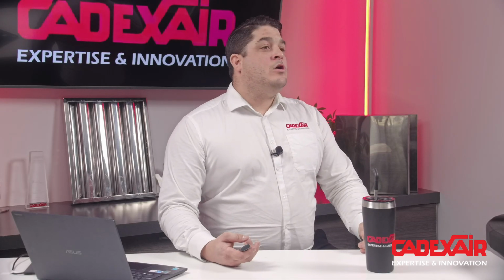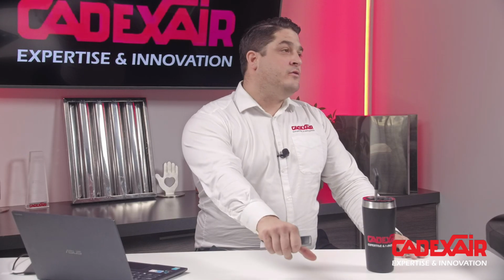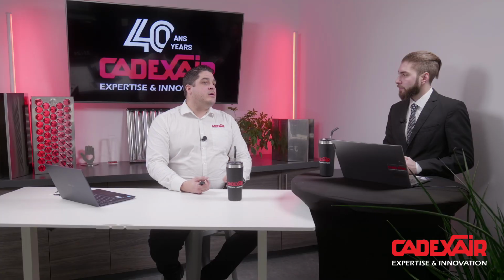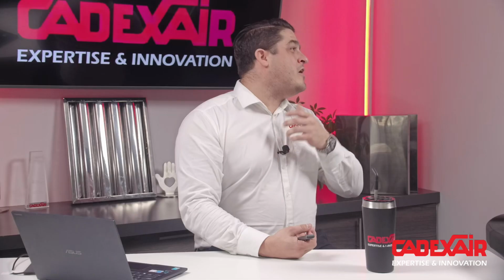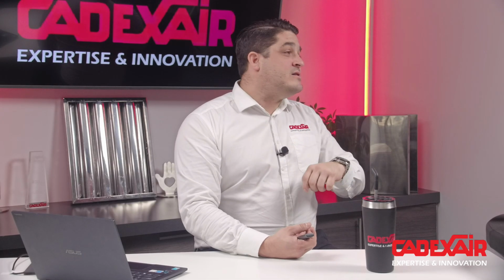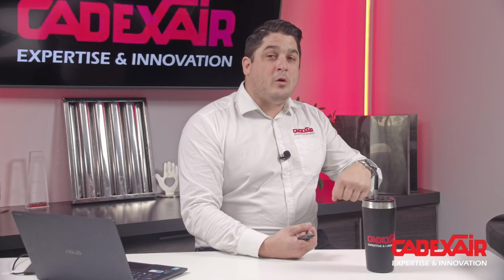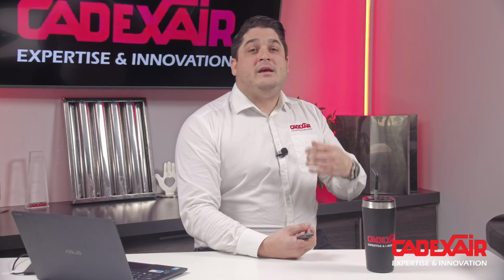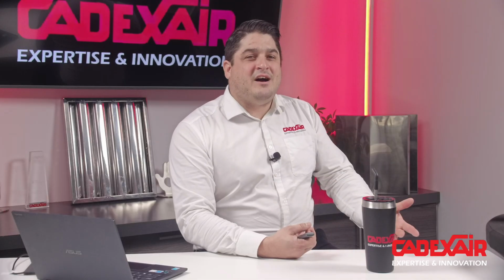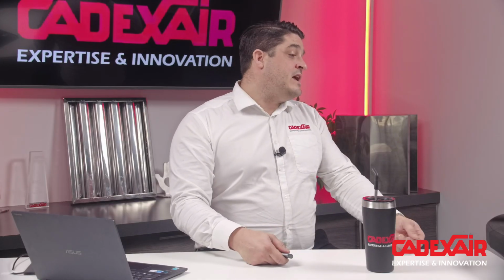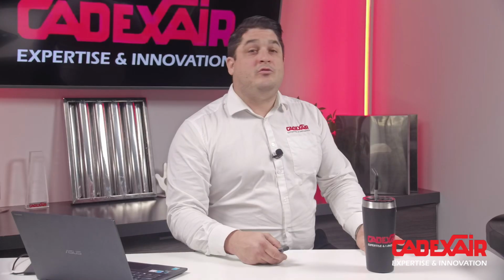So the dog collar, to put the UL label on the hood, we need to have a dog collar. It's part of what we call the follow-up procedure. UL comes to our facility 4 times a year, unannounced. So if they see a hood without a dog collar with a label, they can give you maybe not a fine, but they can give you a new process to follow, and if we don't follow the process, they can remove our listing. So we want to do it right.